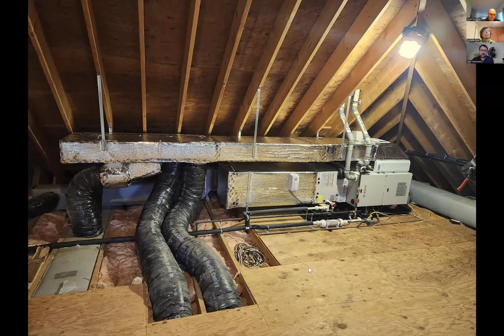The standard ducted systems are also able to be installed as hybrid systems, where in colder climates the heat pump is not always an option, then it can be run as a hybrid. In this case, we have a gas-fired high-efficiency condensing furnace installed with the heat pump itself, which will switch over the heating at -5 degrees outside, and then it switches over to the gas-fired furnace as the secondary stage. It's one option out there, specifically if the house cannot be insulated to the proper level, because the heat pump does require proper insulation on the house itself.